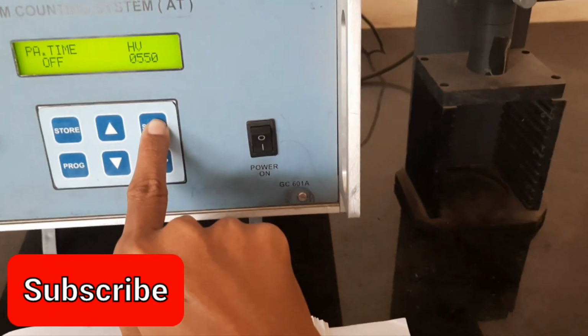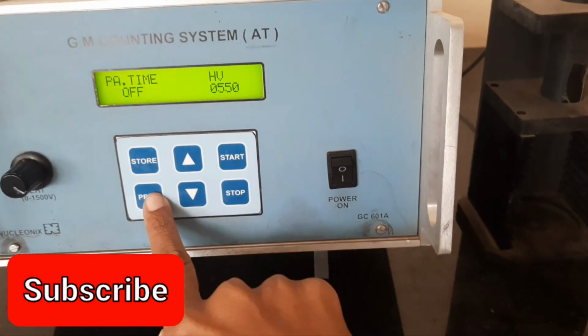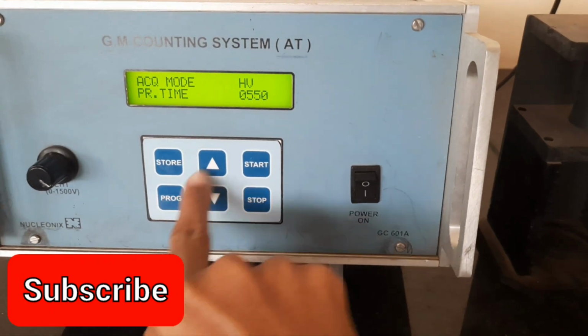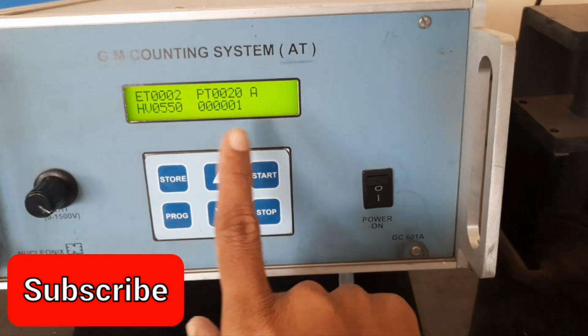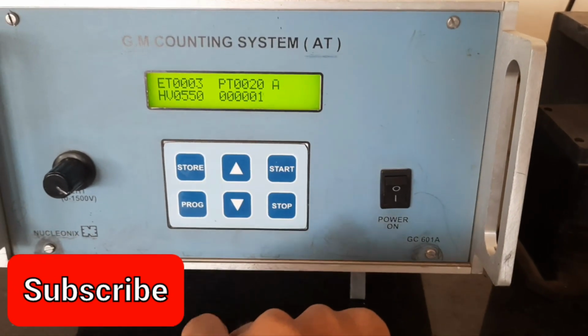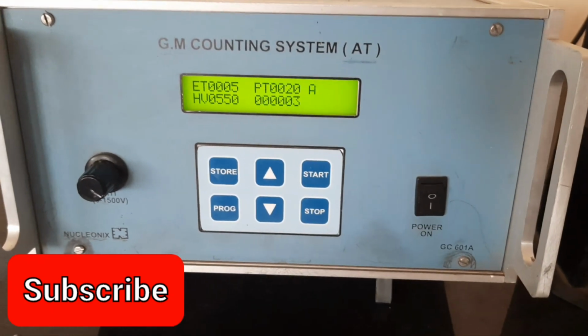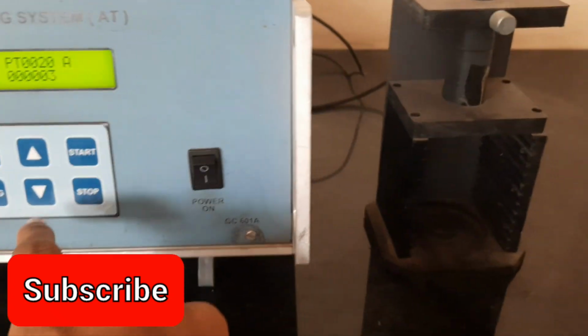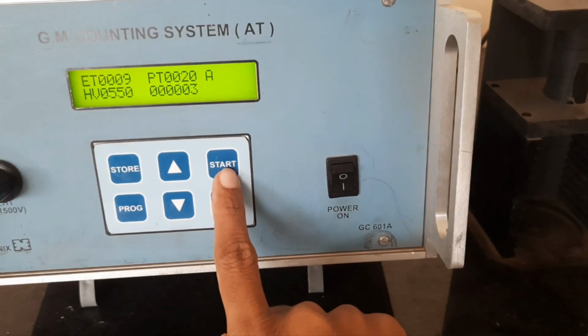Here you should note down the background counts without source. Just click on start to note down the background counts. The counts are going to be very few because we are taking them without the source. Just note that down.